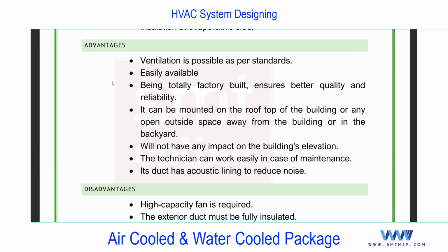Water cooled is limited. But if you talk about, you see, generally package means generally people are thinking of air cooled package only. Water cooled, as I said, na, is just available with a few makes only, not in all locations also. So easily available, I'm talking about this air cooled side. Next, it's a factory assembly, so you can expect the quality. On site, we need to go for the ducting, installation of ducting side, but the refrigerant piping and all, we are not disturbing anything except this.